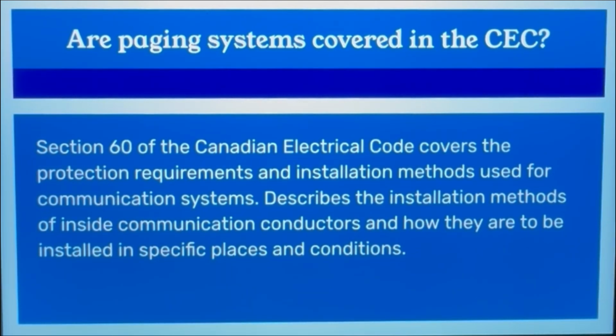It is important to know how to properly ground your communication system as well, covered in Section 60-704 and in Section 60-706. It is important that these code rules are followed and your communication system is properly grounded, because if your communication system is connected to a separate electrode from the building power service grounding electrode, then a lightning strike on or near the building can cause conductive parts of the equipment in the communication system to rise and cause voltage spikes and sometimes fires.